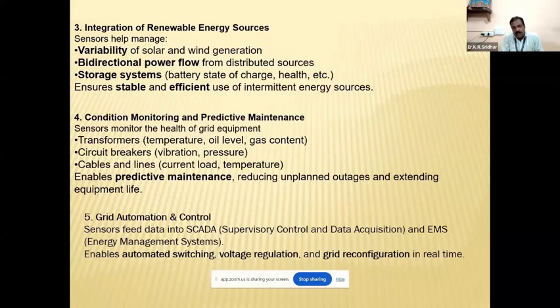Sensors are used for condition monitoring and predictive maintenance, for equipment protection and monitoring. For transformers, temperature, oil level, and gas content are monitored automatically. For circuit breakers, vibration, pressure, and SF6 pressure are sensed. In cables and lines, sensors detect load current and temperature. This enables predictive maintenance, reducing unplanned outages and extending equipment life.